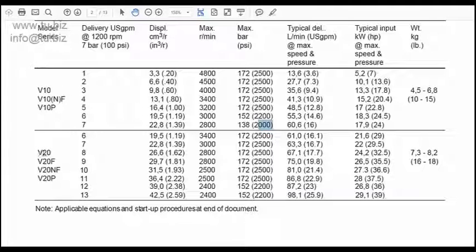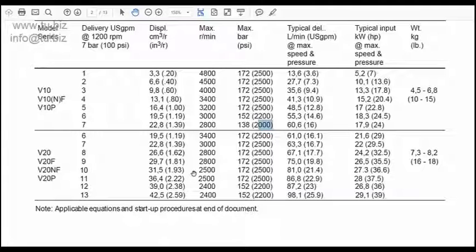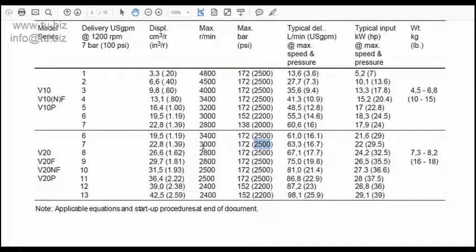Since I don't want a smaller pump, the next option is to jump from the V10 series to the V20 series — a bigger frame, a little more cost, but given the technical requirements I want a pump that delivers both the flow and the pressure. In the V20 series, there's a 1.39 cubic inch option — bigger than what I calculated — and it gives 2500 PSI. I'd pick this one because it has the displacement, pressure rating, and RPM I'm looking for.